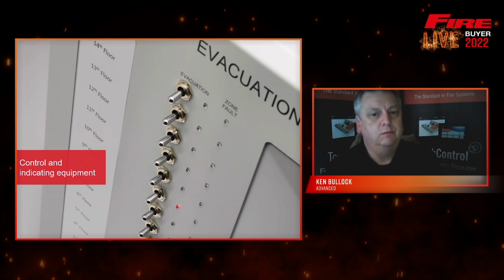And that is, again, another reason why it's not suitable to have those automatic fire detection devices, or indeed those outputs for lifts, alarms, etc., connected to it. It's fair to say that because of that simple operation, a remote connectivity to a third-party monitoring center for fault monitoring would be very advisable, purely because without that, there is no way for anyone to know when a fault develops on this system, apart from the maintenance, which we'll come on to in a little bit.